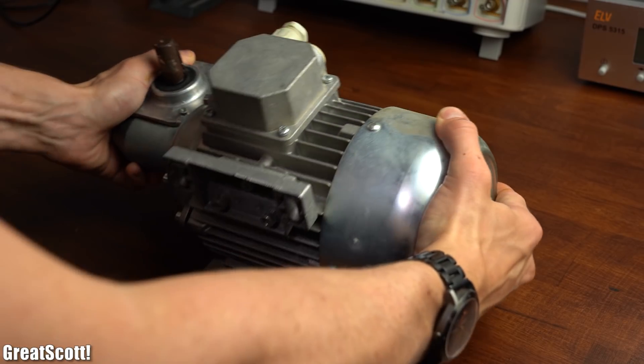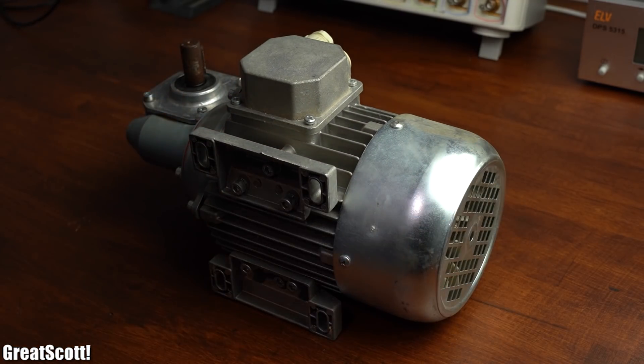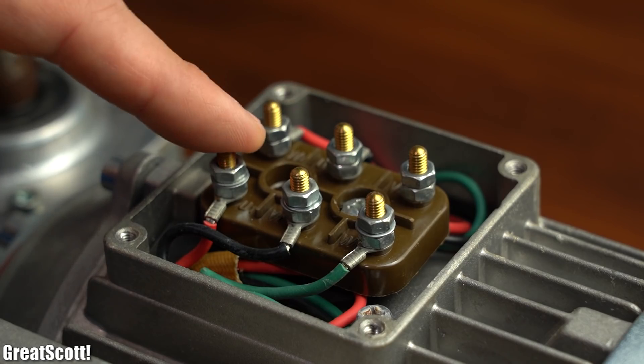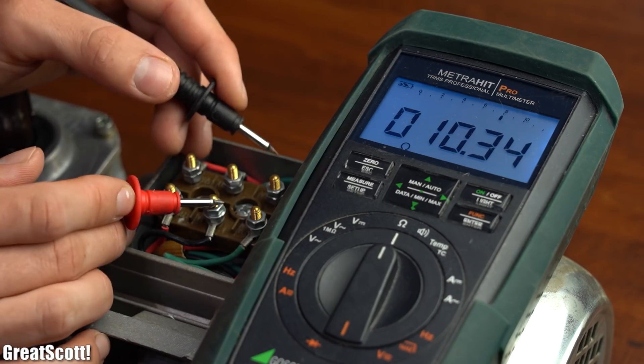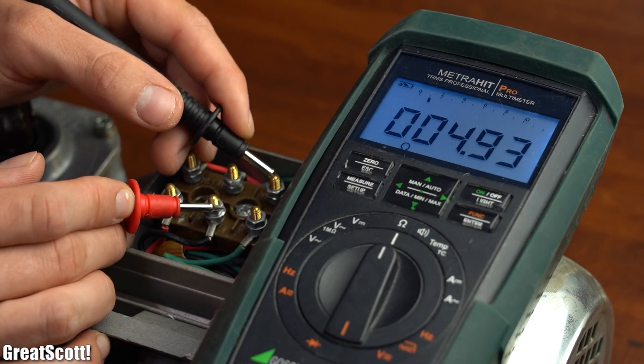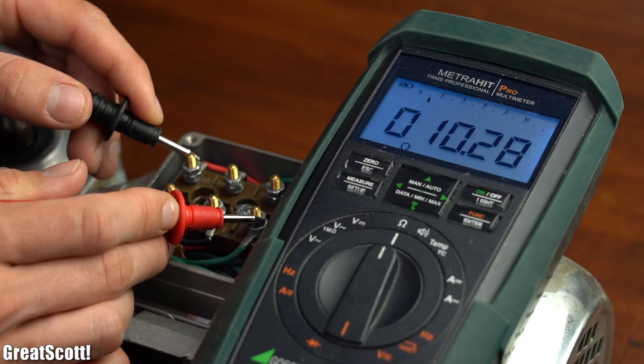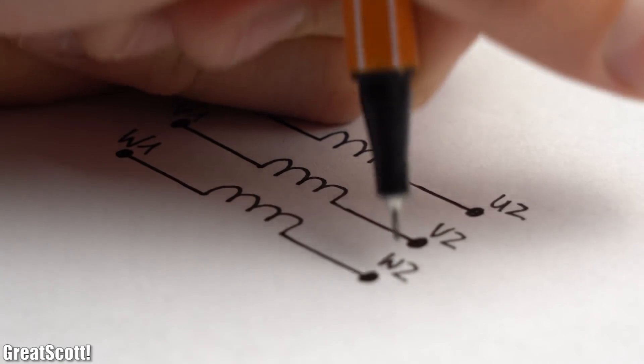First off in order to understand how this motor works I opened up its terminal box and was promptly greeted by 6 connector wires. Through the help of my multimeter I found out that the wires U1, U2, V1, V2 and W1 and W2 all form a separate coil.